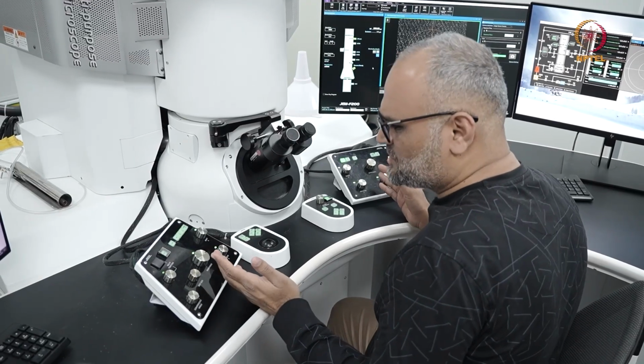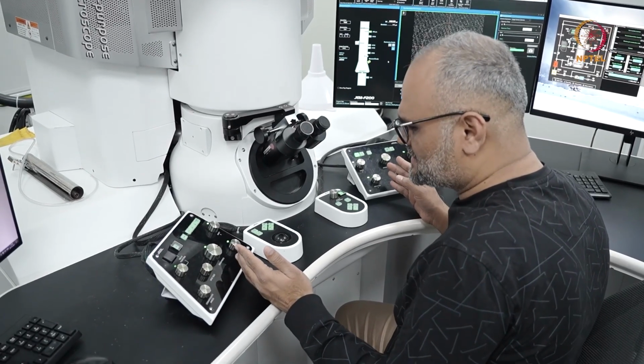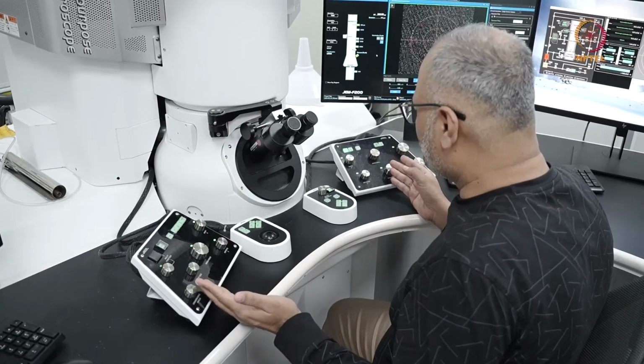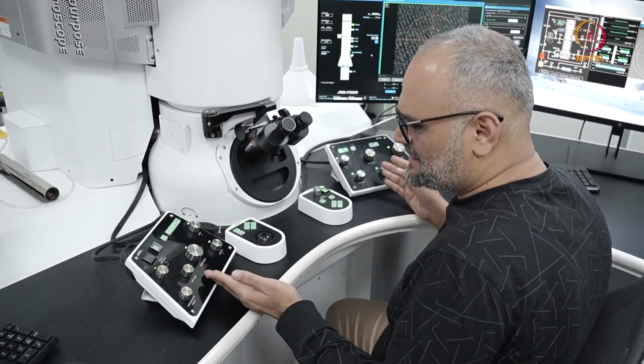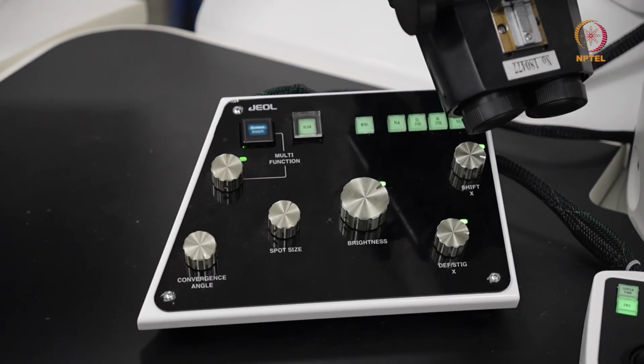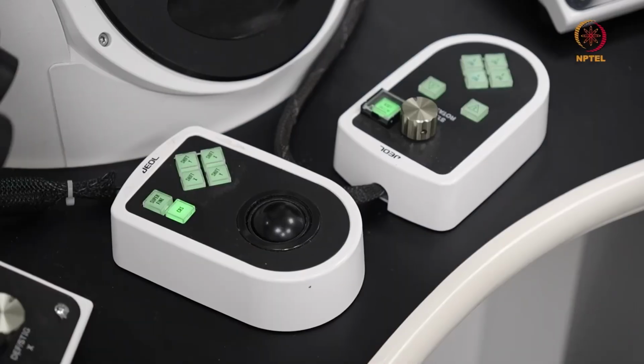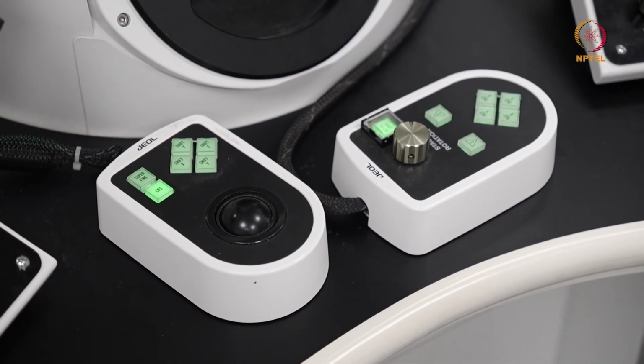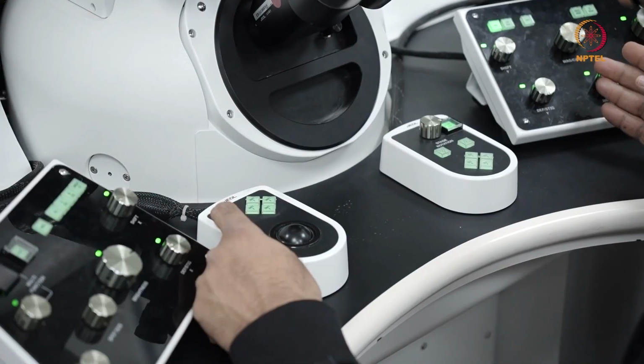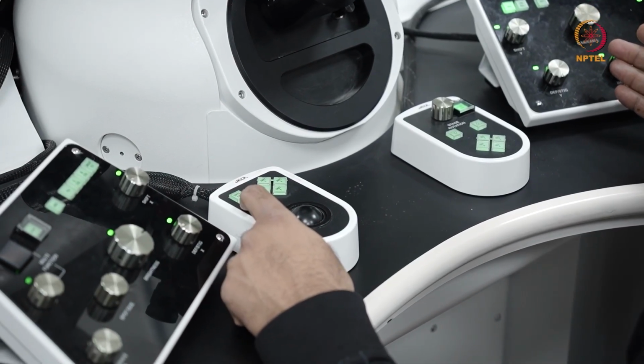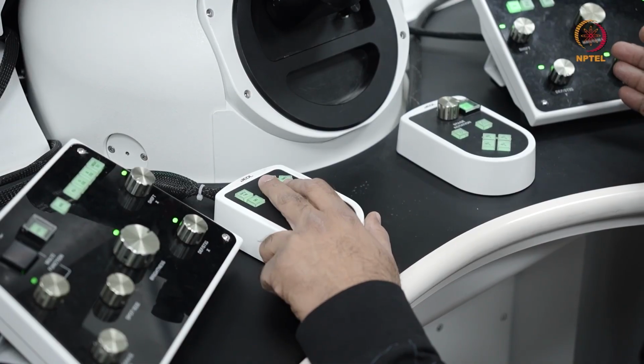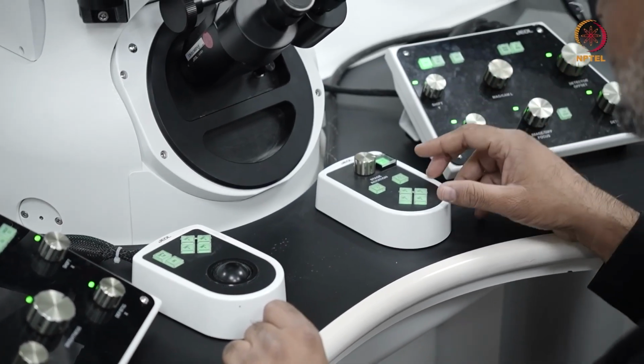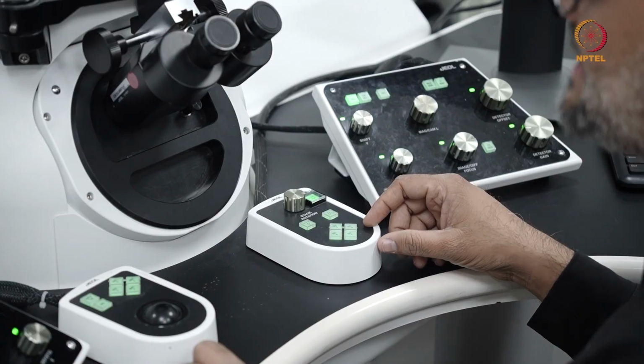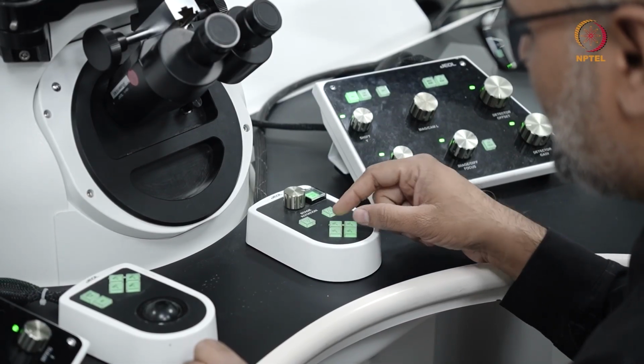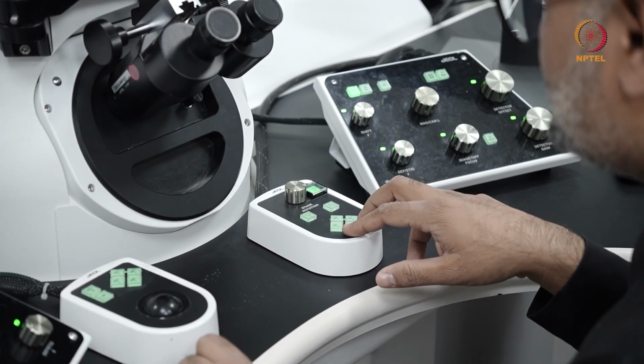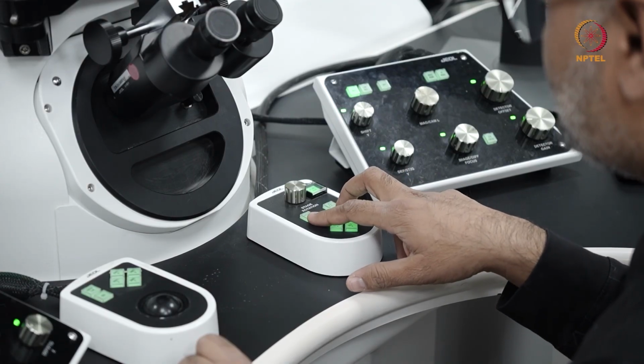Okay. Now we'll look at the layout of the console. So this instrument has a slightly different layout on the console. You have these 4 parts of the console. The left panel, you have a few knobs, and then you have the tracker ball here, which is used to move the stage. You can choose the piezo control by selecting the superfine or coarse for doing coarser movements. You also have the shift X and shift Y knobs here. And then for tilting, you do not have the pedals like you have on the other instrument. Over here you have the tilt Y and tilt X buttons here, and this is to adjust the stage height.